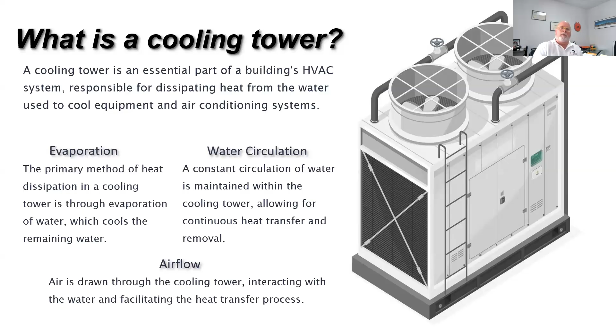Typically here in South Florida, we design for water coming in at about 95 degrees from our building and leaving at about 85 degrees. That's typically what we see with cooling tower designs here. So the big thing is a cooling tower is the mechanism by which we ultimately reject heat from our building.